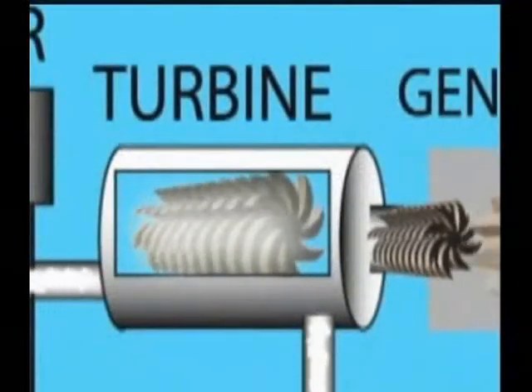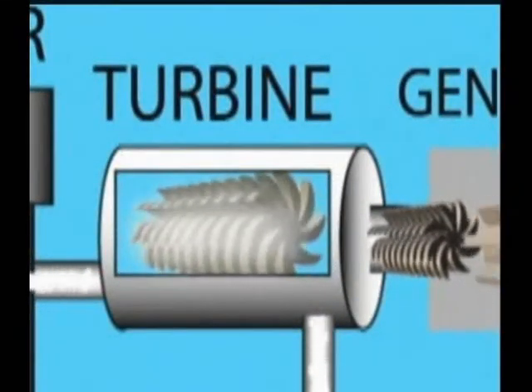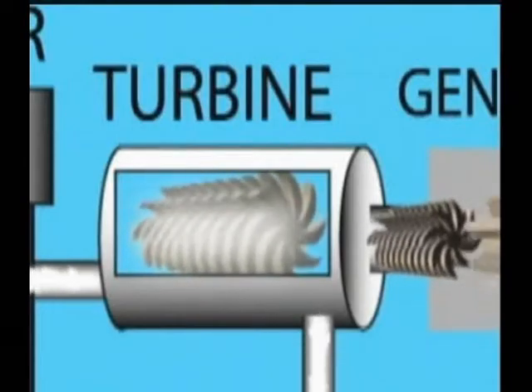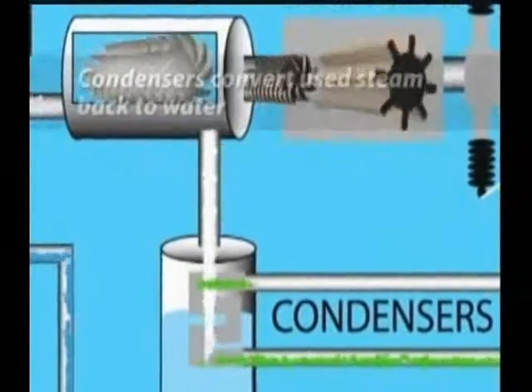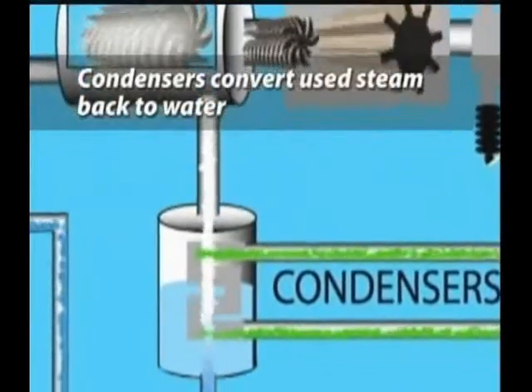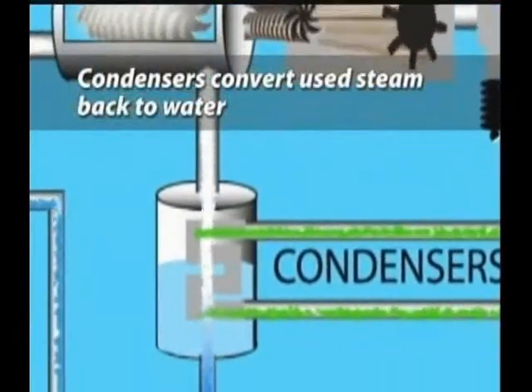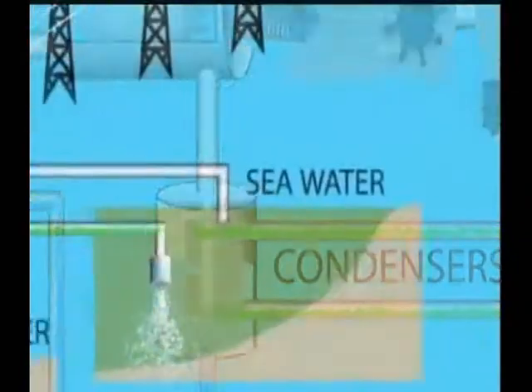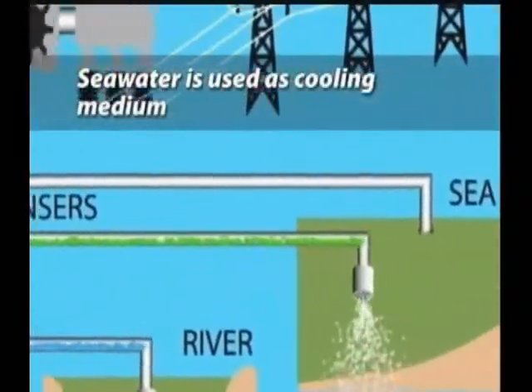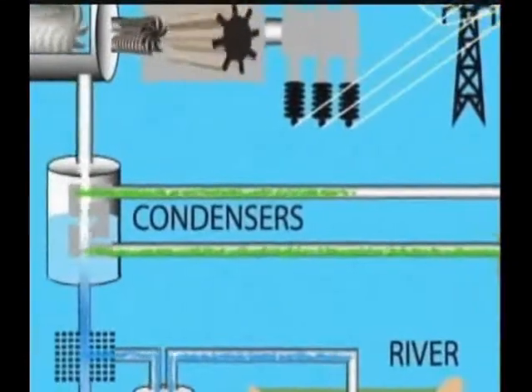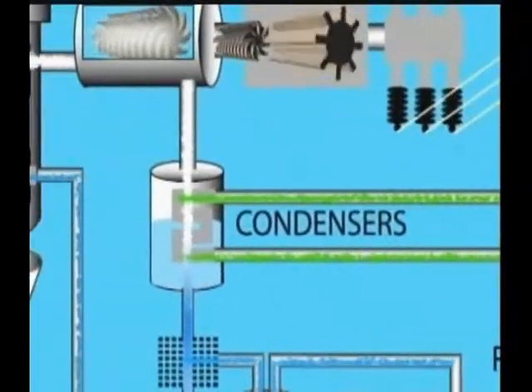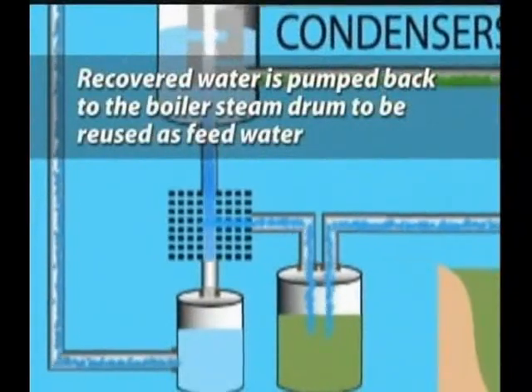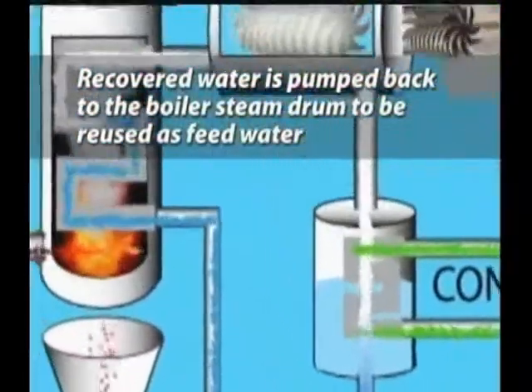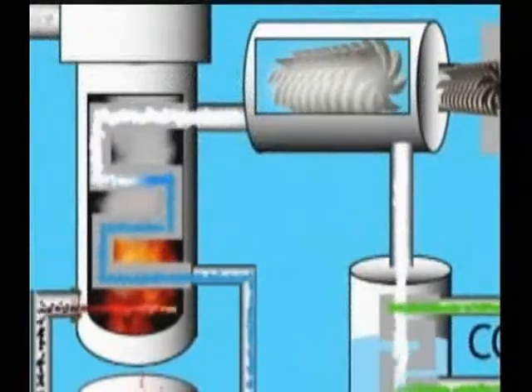Steam leaving the turbine is at much reduced pressure and temperature, its energy having been dissipated in driving the turbine. Steam discharged from the turbine passes through condensers, which convert the steam from vapor to liquid through condensation using seawater as a cooling medium. There is no direct contact of steam to the seawater. The recovered condensate or water is pumped back to the boiler steam drum for reuse as boiler feed water.